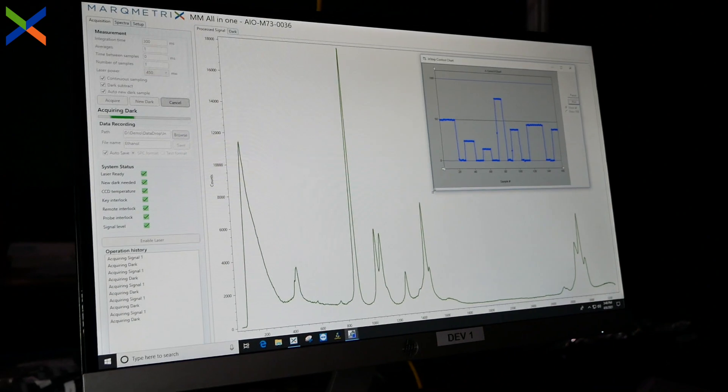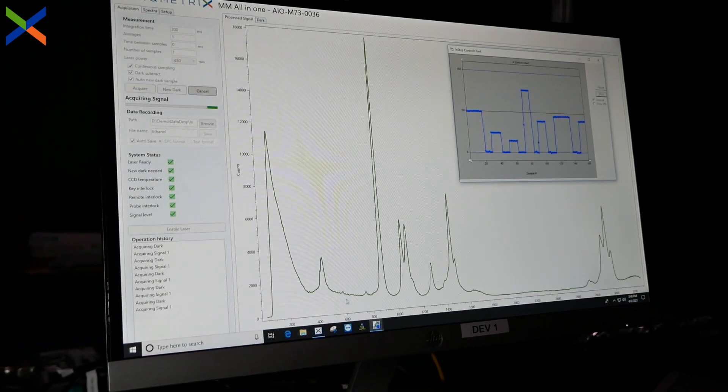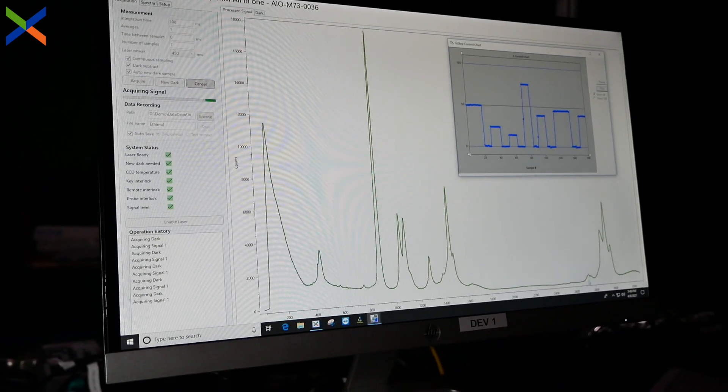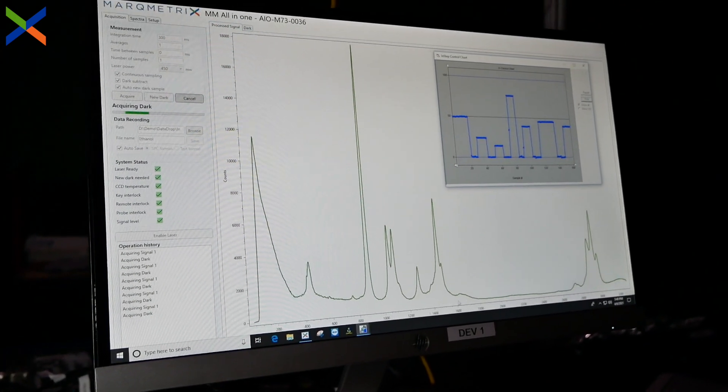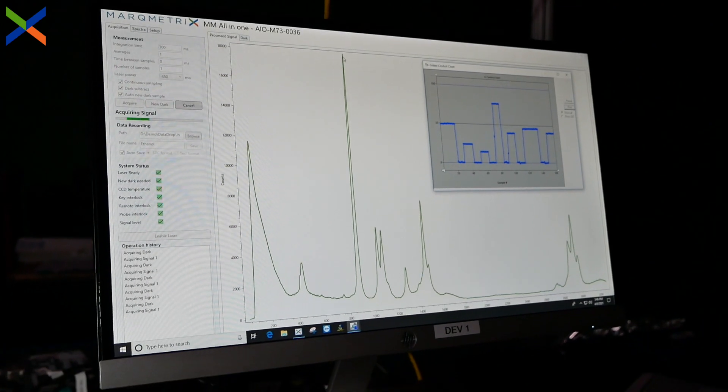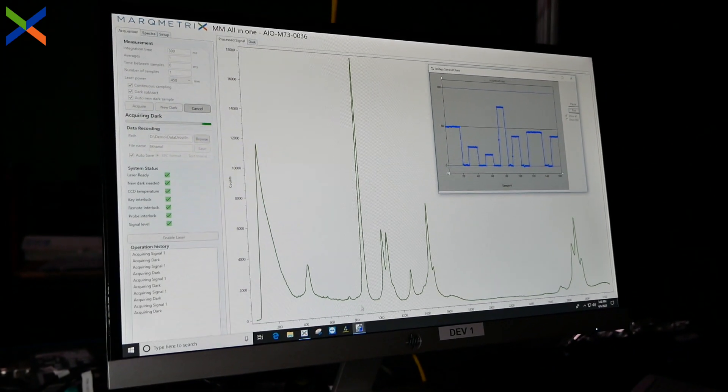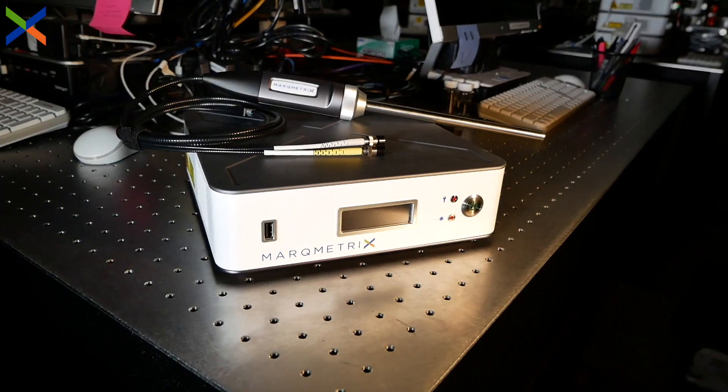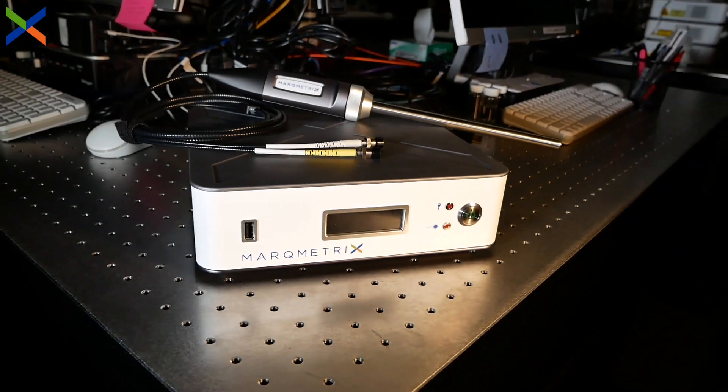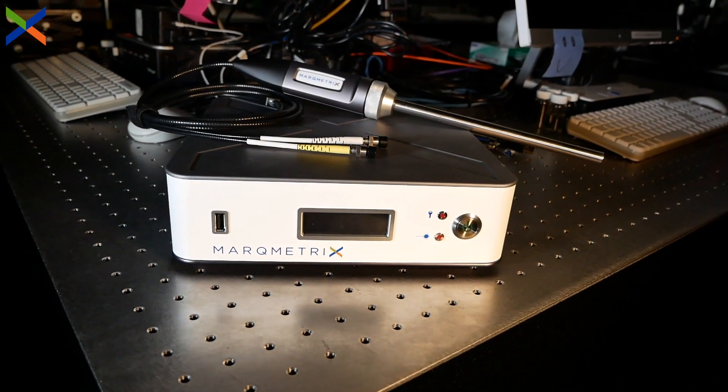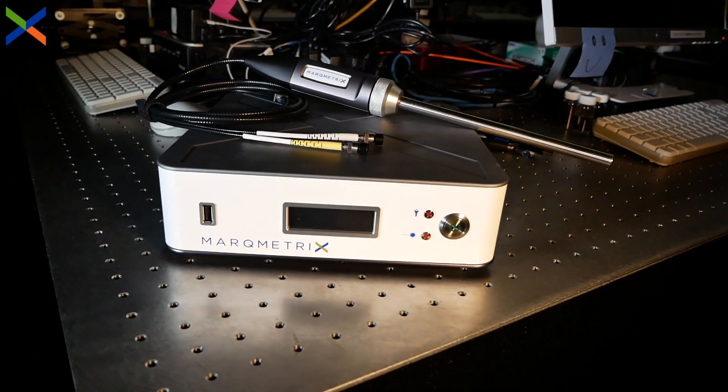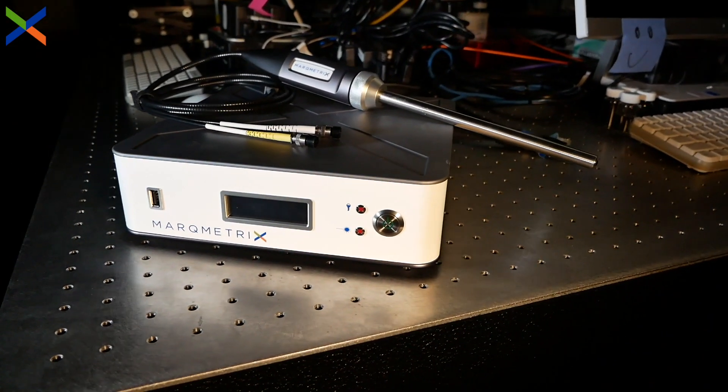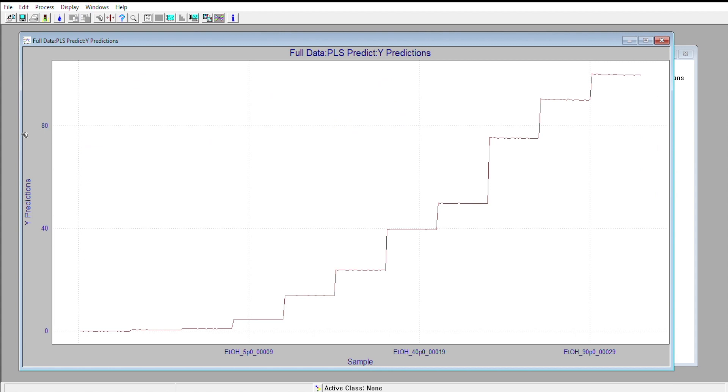These predicted values can be fed into a controller using OPC or Modbus protocols, enabling the critical process data to be transmitted throughout a company or organization. Thanks to the ease, speed, and stability of data acquisition made possible by the MarqMetrix all-in-one Raman system, building an accurate predictive model is incredibly easy.